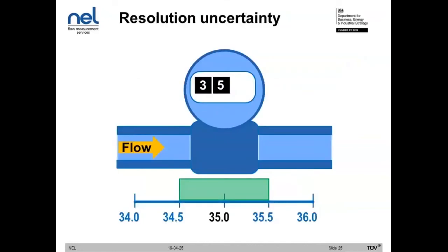So to give an example of this, we have a flow meter, and this flow meter isn't very precise. It only reads to the nearest whole unit. So this might be 35 litres per second, for example, or kilograms per hour, or any type of flow unit. But the point is, we can see the resolution is extremely limited. With this type of resolution, we cannot differentiate between values of 34.5 and 35.5. In each case, the reading will just be 35. So we have a very large window of resolution uncertainty as a result of the reading and the display of this device.